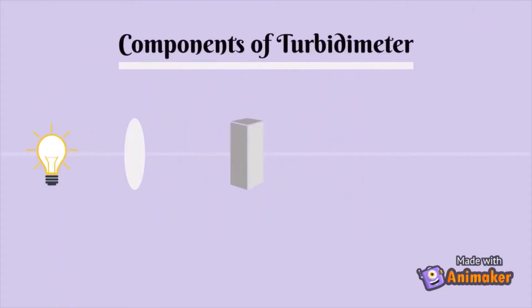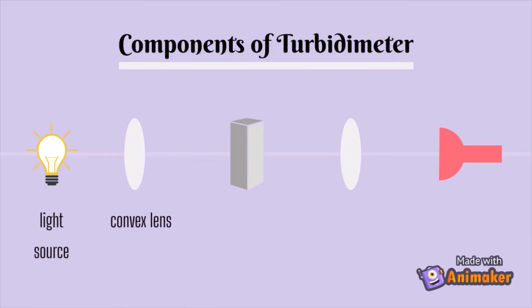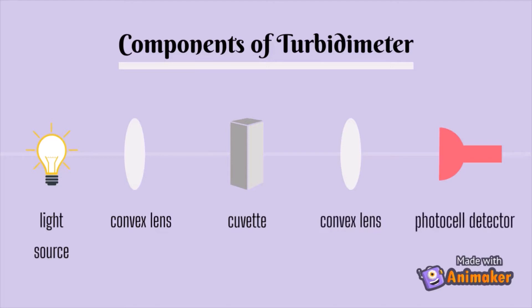Turbidimetry consists of a light source that emits wavelengths near the ultraviolet range, a convex lens to collect and direct a beam of light coming from the light source, a sample holder or cuvette, another convex lens to collect the transmitted beam of light, and finally a photocell detector or a photo tube, and a read-out meter to measure the amount of transmitted light.